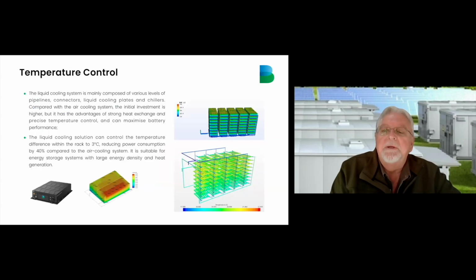With these thermal images, you can see how efficient liquid cooling technology is. The temperature is controlled to stay between 20 and 21 degrees Celsius at all times. The maximum temperature difference between the batteries in the racks is below 3 degrees Celsius. With liquid cooling technology, the base power consumption is reduced by 40% compared to an air cooling system, and it is suitable for energy storage systems with large energy density and heat generation.